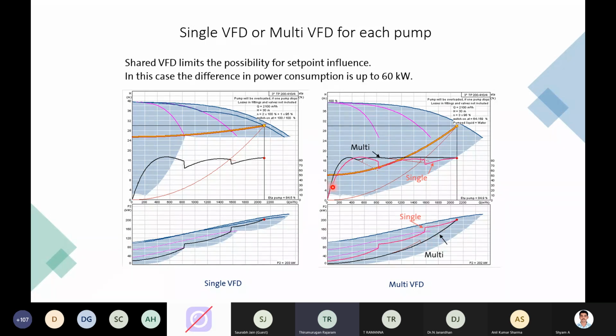And second, you can find the multi VFD will have a very smooth operation in terms of your pressure buildup. So there will not be any sudden surge in your lines. It will be a very smooth ramp up, attaining your required flow steadily, we can say. So all of that you can avoid in this case. And also when you compare the efficiency, you can find the efficiency is much better for multi VFD than for single VFD. Whenever the varying flow picks up, the efficiency is low for single VFD, whereas here we try to maintain the same efficiency in the multi VFD option.